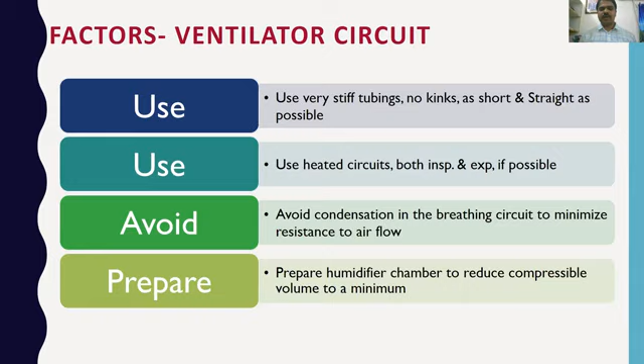Use a heated circuit, both inspiratory as well as expiratory if possible. Earlier we were getting an expiratory one which contained a water trap. Now the expiratory one also contains inline heating. I'll show you that one. And avoid condensation in the breathing circuit to minimize the resistance to airflow. There should not be any condensation, because even small droplets can hamper your high frequency.